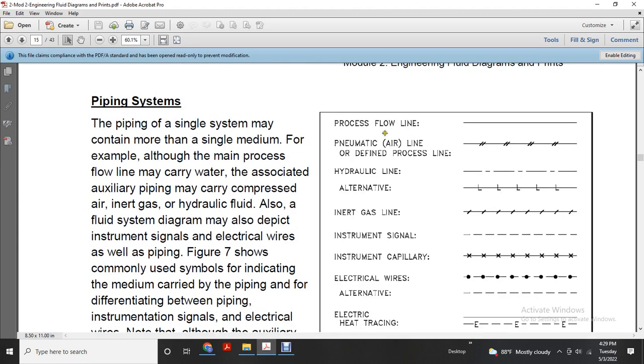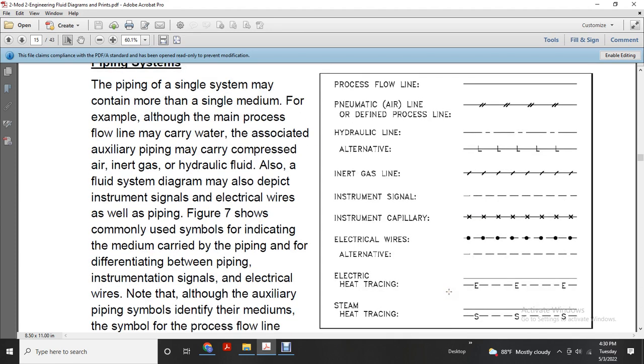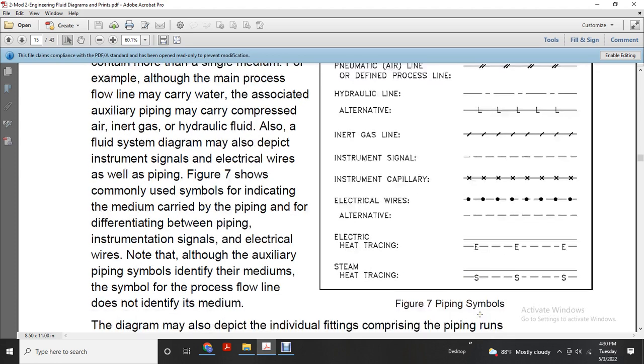First we show the process flow line, then the pneumatic air line, defined with two dashes in line, the hydraulic line, a short and a long dash, and then an alternative would be a short line with L's crossed out crossing the line. For air or gas, a single dash instead of a double dash, single crosshairs. Instrument signals, small dashes. Instrument capillary, X's dashed. Electrical wire, dot dash, alternative smaller dashes. Electrical heat tracing, a straight line with E's on the dash, and steam heat tracing, S on the dash line.